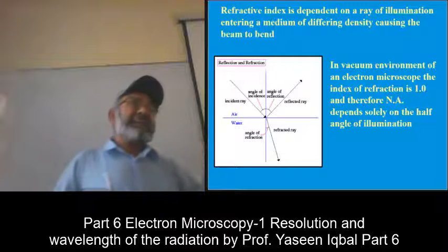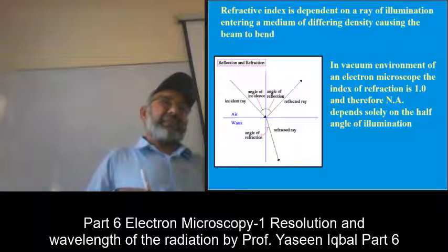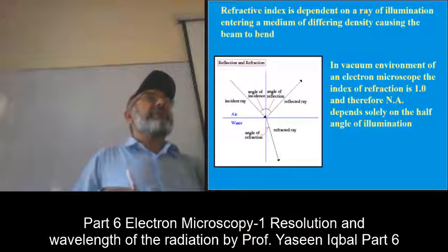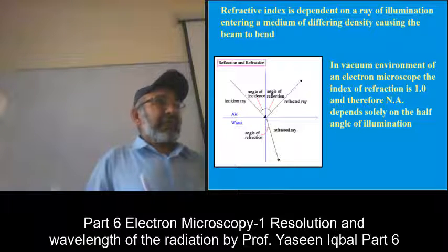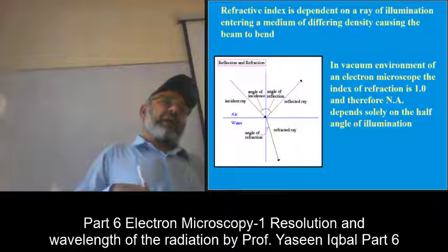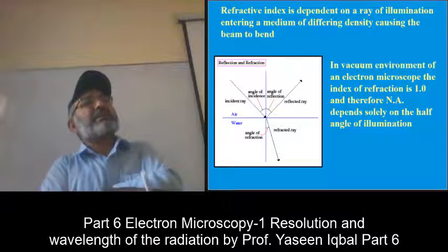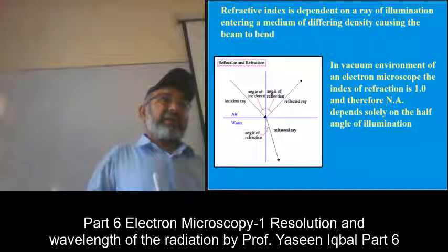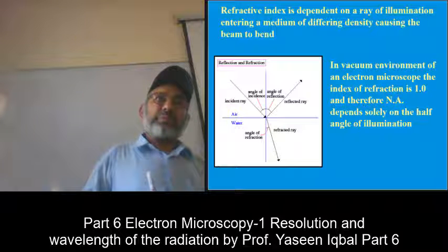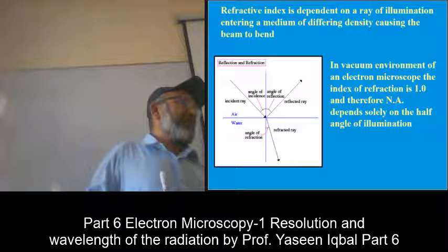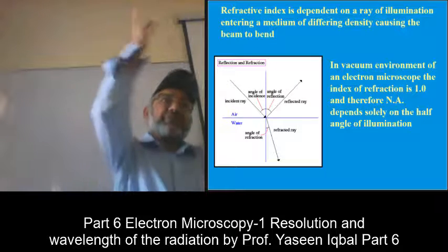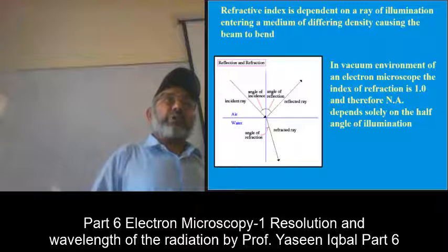Similarly, if fewer electrons are backscattered, the illumination will be less, right? That particle, that grain will appear a bit darker in comparison to the other. But if all the electrons are absorbed, then you will see a complete dark feature. And that will be a pore or a very huge dip inside the material, a crack inside the material, where all the electrons are absorbed and they are not coming back upwards.